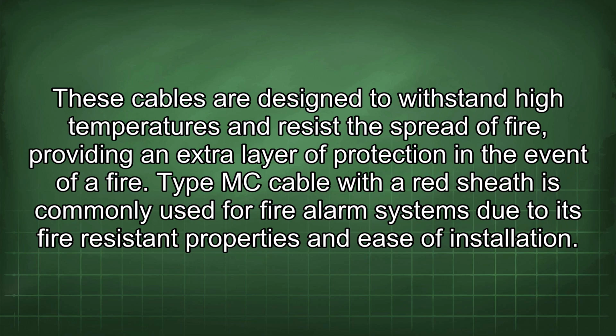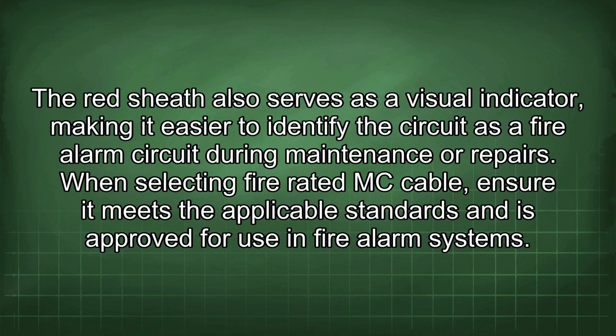Type MC cable with a red sheath is commonly used for fire alarm systems due to its fire-resistant properties and ease of installation. The red sheath also serves as a visual indicator, making it easier to identify the circuit as a fire alarm circuit during maintenance or repairs. When selecting fire-rated MC cable, ensure it meets the applicable standards and is approved for use in fire alarm systems.